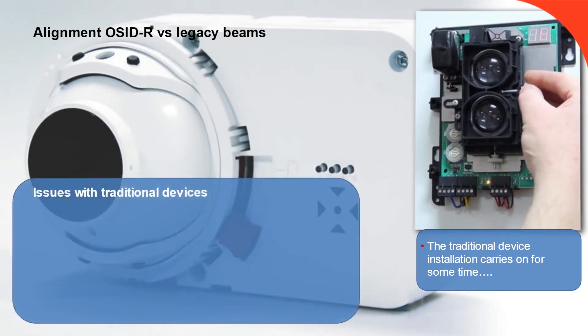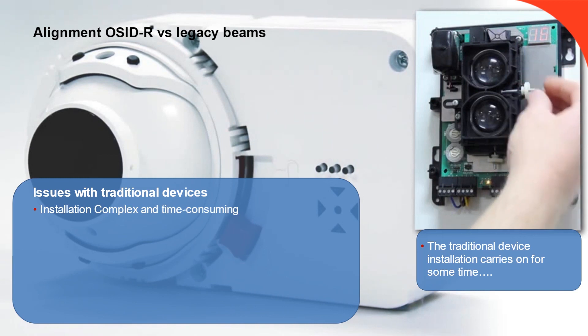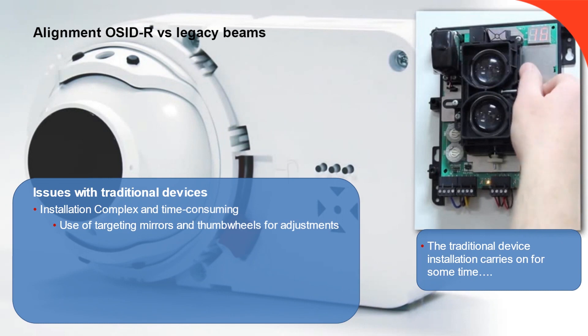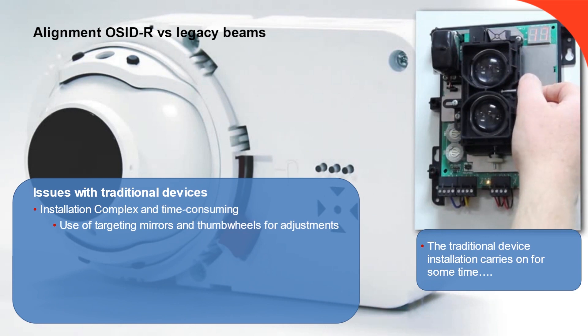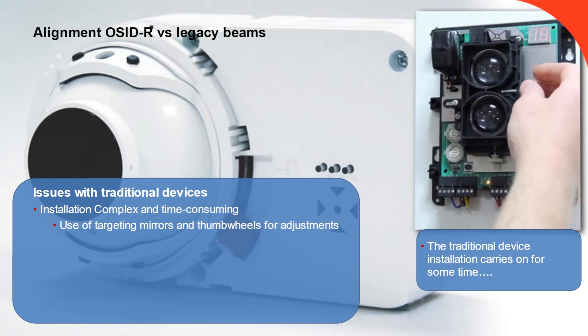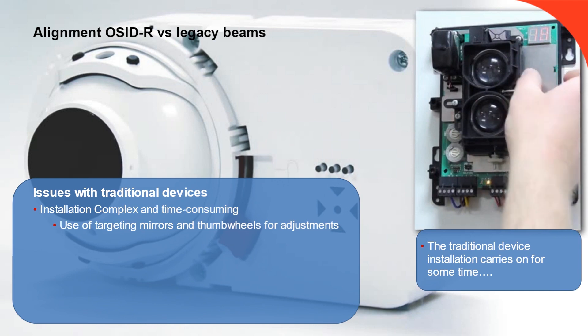The 6500, or 1224 in this case, uses a targeting mirror to enable the initial alignment. This is a clever process allowing the installer to get an accurate facsimile of the device's line of sight. However, the system requires the operator's head to be held in exactly the right place to properly see the target — this isn't always easy, particularly up a ladder. A brightly coloured piece of paper is supplied with the 6500 to be stuck on the reflector, enabling the initial coarse adjustment. Following this, the paper must be removed from the device — best get the ladders out again.